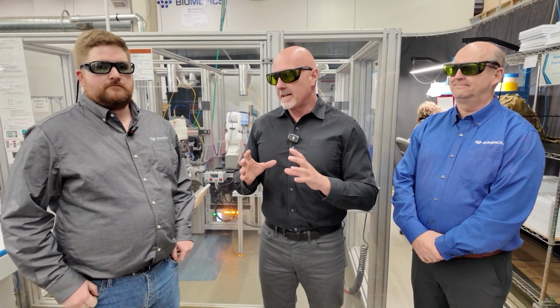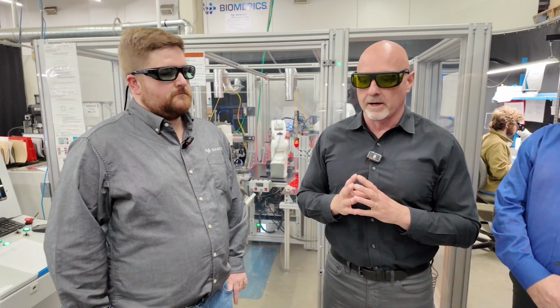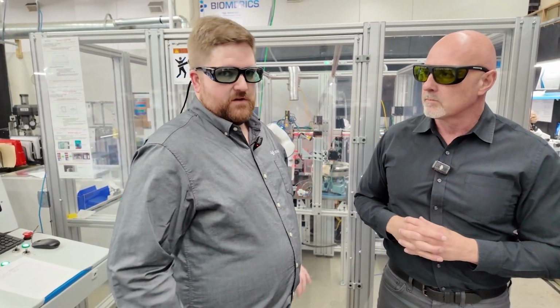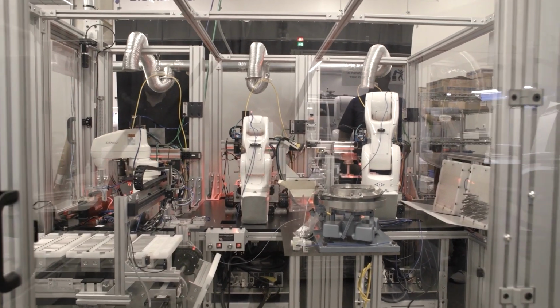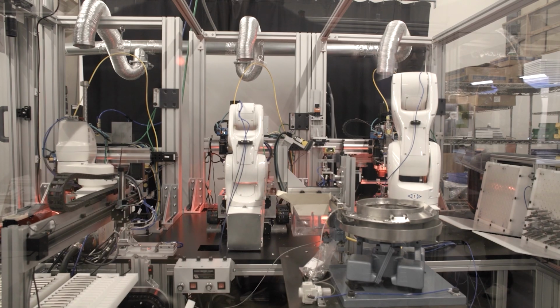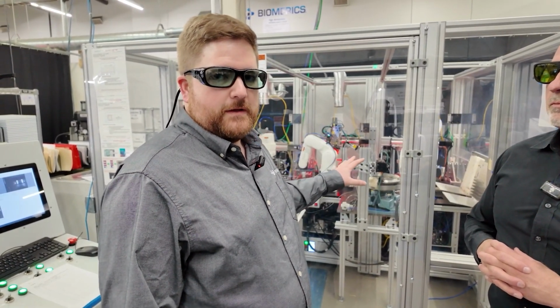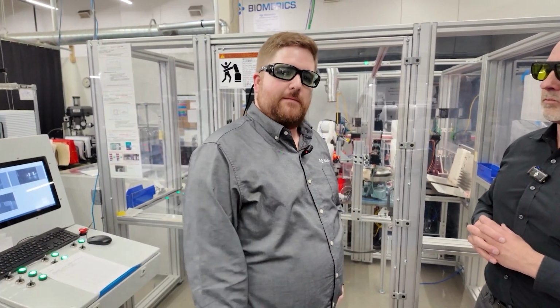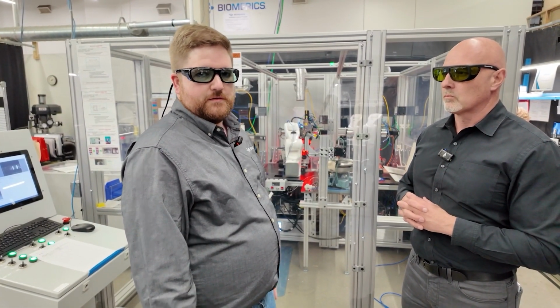Absolutely. Mike, Ken did a good job giving us a high-level overview of the automation capabilities here at Biomerics. Can you dig a little deeper for us and talk about a specific application? Yeah, so behind us we have an application that Ken was talking about just before. This is a lower volume prototype product. The volume increased. We had a semi-automated vision-guided welder that we ran this on for many years. And then as the volumes went up, we decided to fully automate it. So what you see behind here is basically all the steps that were taking place in a more manual or semi-automated approach. And we took all those and applied robotics and vision to get the cell you see behind you.